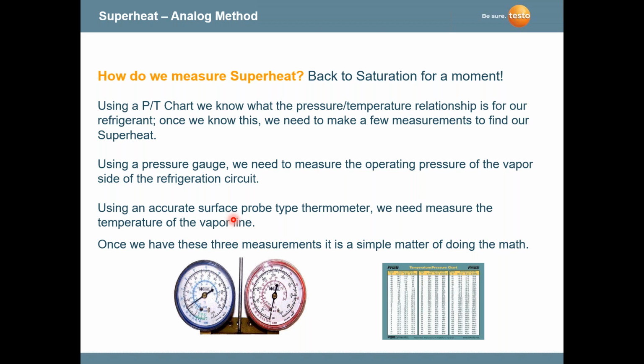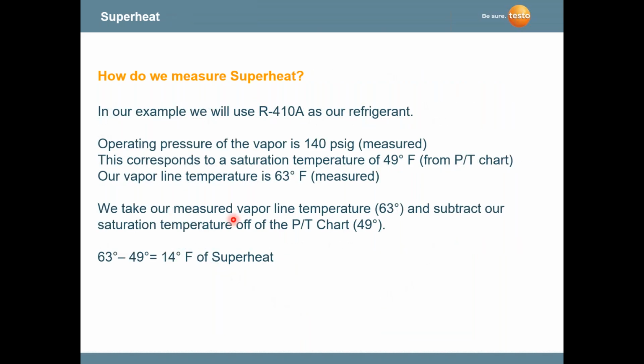If we go back to the analog method, we're all familiar with the analog method where we use pressure temperature conversion charts. We use a pressure gauge and an accurate thermometer. We're using the measurements and doing the math to calculate the superheat. In this example, we have 410A. Let's say we have a low pressure of 140 PSIG, and PSIG is gauge pressure.